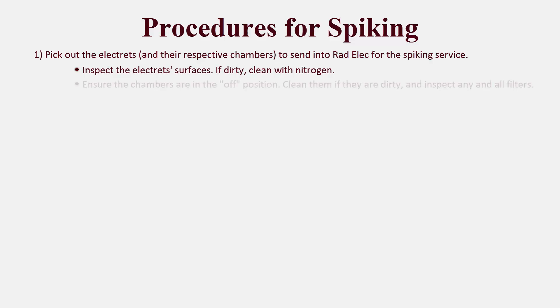Let's move onward to the specific procedures for spiking. The first step is to pick out the electrets and their respective chambers to send in to Rad Elec. Inspect the surface of each electret to make sure that it's clean — if not, clean it off with nitrogen. Also, inspect the chambers you're going to use, make sure that they're in the off position, and that any filters in those chambers are in good condition.